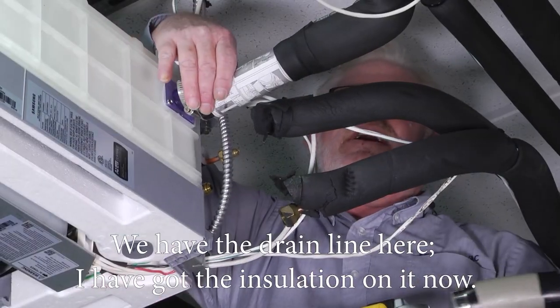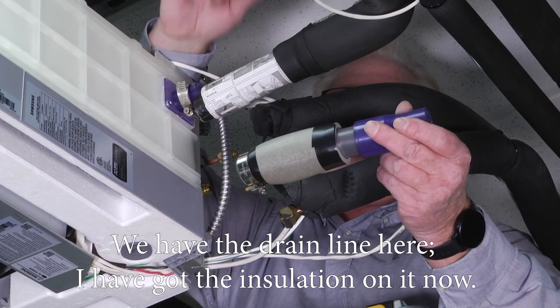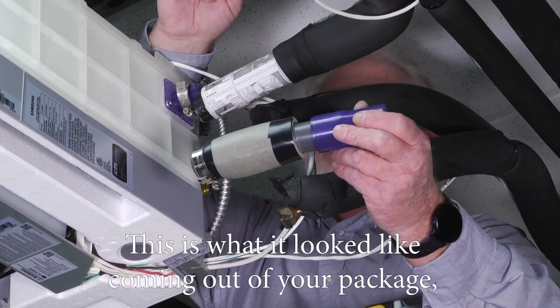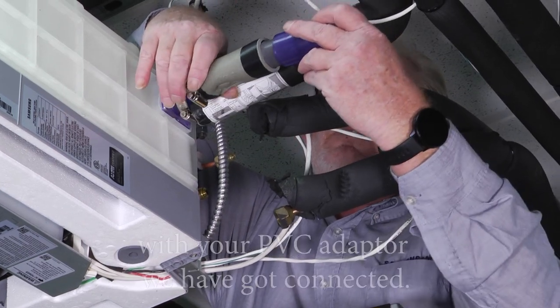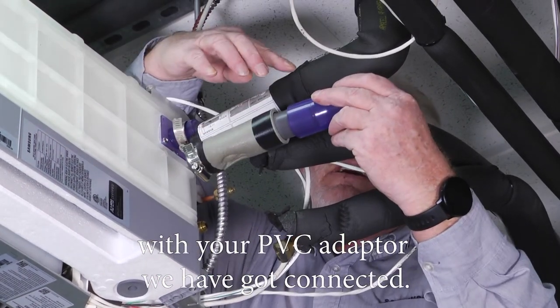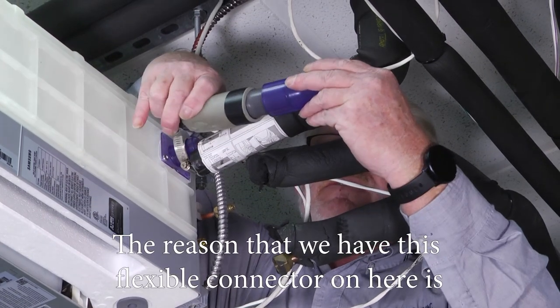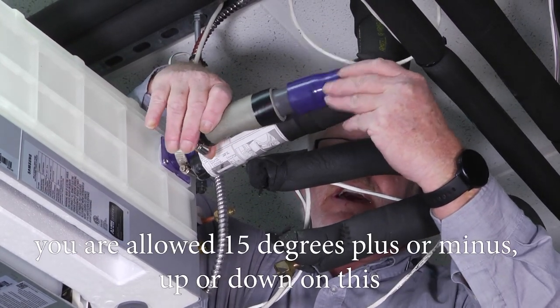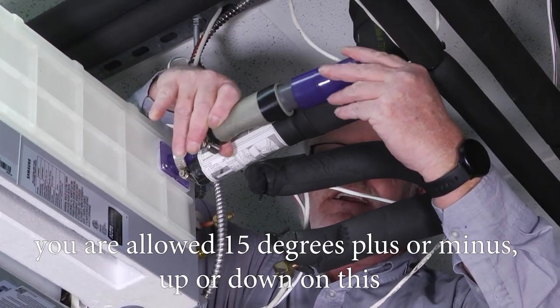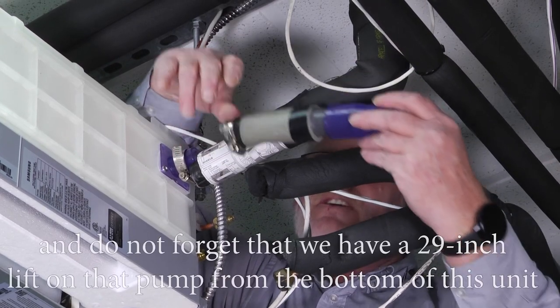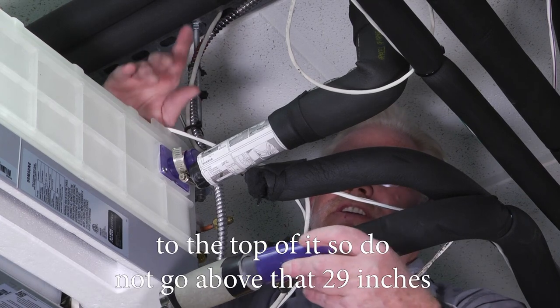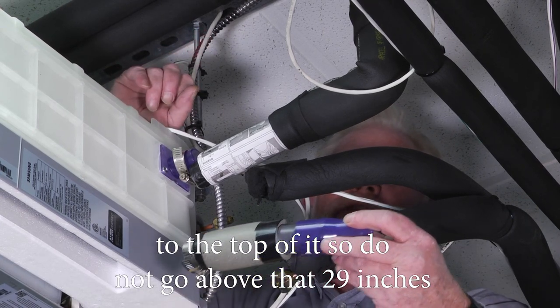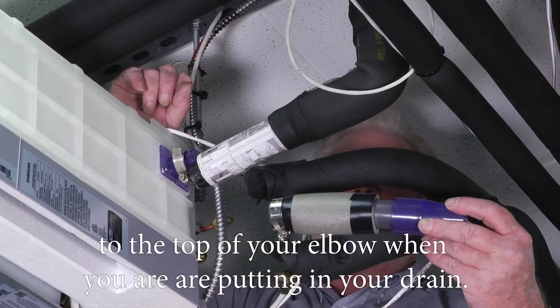We have the drain line here. I got the insulation on now. As you'll see, you've got a flexible connector here with your PVC adapter connected. The reason why we have this flexible connector on here is you're allowed 15 degrees plus or minus up or down on this. Don't forget we have a 29 inch lift on that pump from the bottom of this unit to the top of it. So do not go above that 29 inches to the top of your elbow when you're putting your drain.